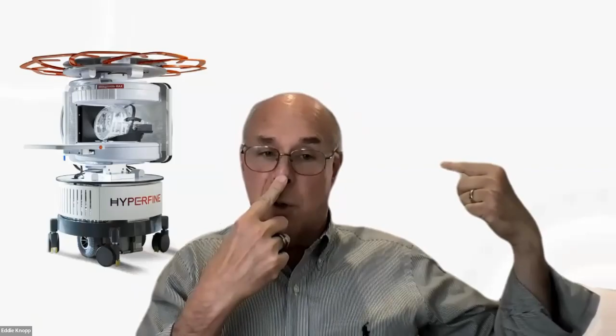But realize, at least on our hyperfine scanner, the 5 Gauss line extends 2.5 feet from the tip of your nose. So the likelihood of the ECMO system itself or a ventilator or a monitor being in that region is basically next to zero. And conveniently, Eddie has a picture of the hyperfine swoop behind him, and the orange mesh at the top of the device is the 5 Gauss line, and you can basically open it up and demarcate that in the ICU environment to see where that is.